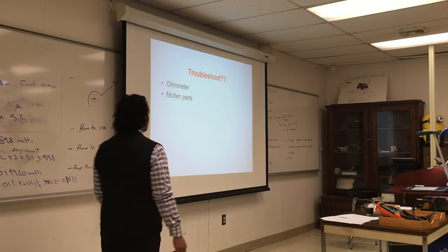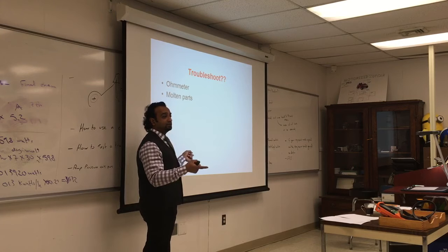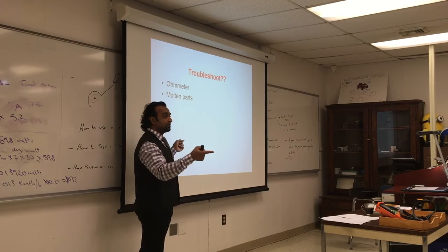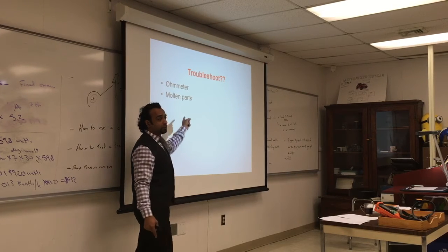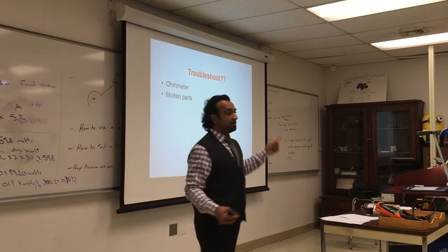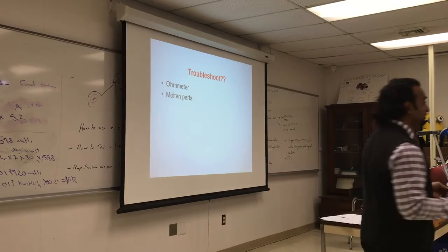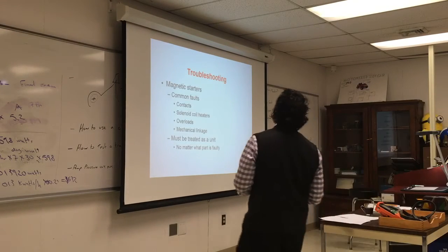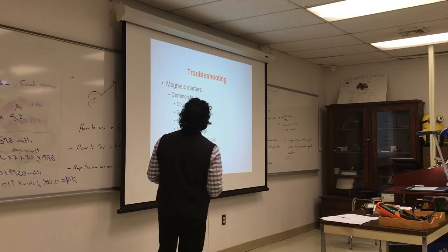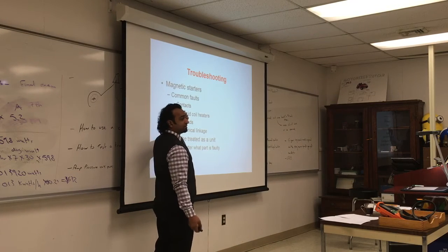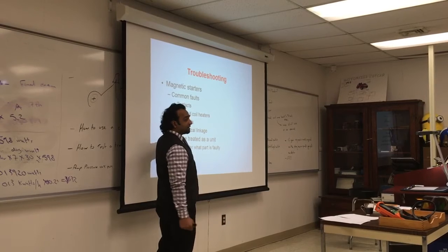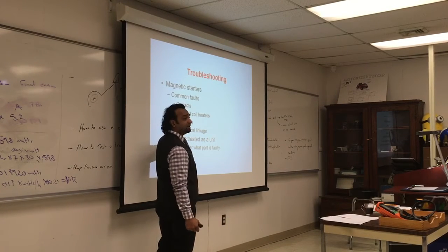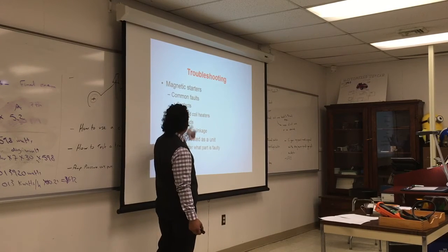To troubleshoot, again, the ohmmeter is your best friend. You go and test the terminals for connectivity. Also look for molten parts. You're going to see if anything melted or discolored or burnt. Again, we always check the contacts. If anything is rattling, something is not right, that means the mechanical linkage has been displaced.